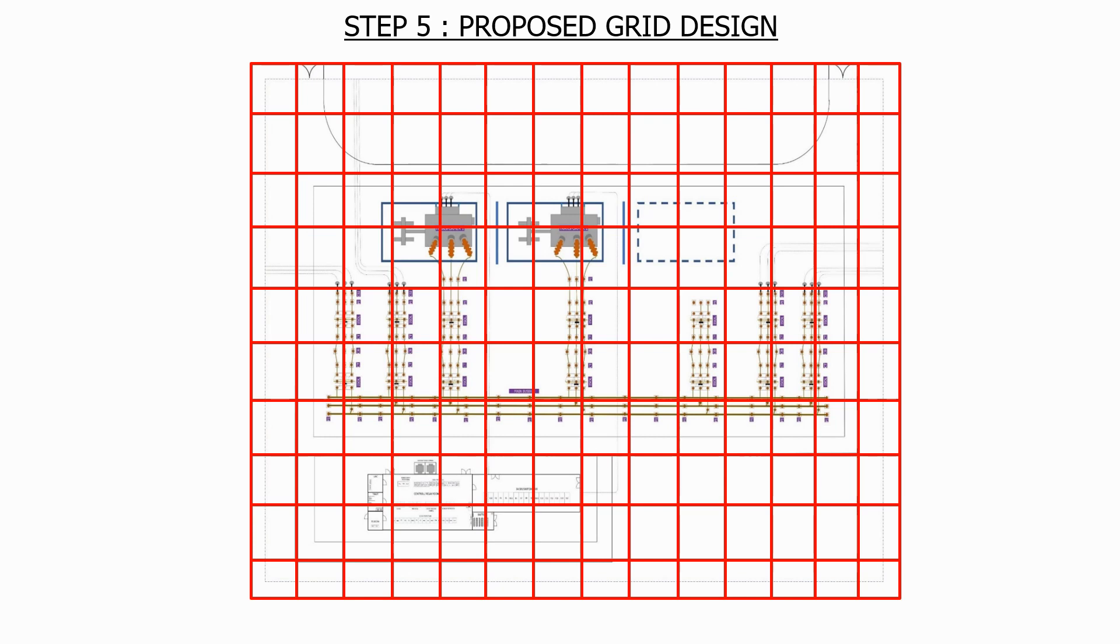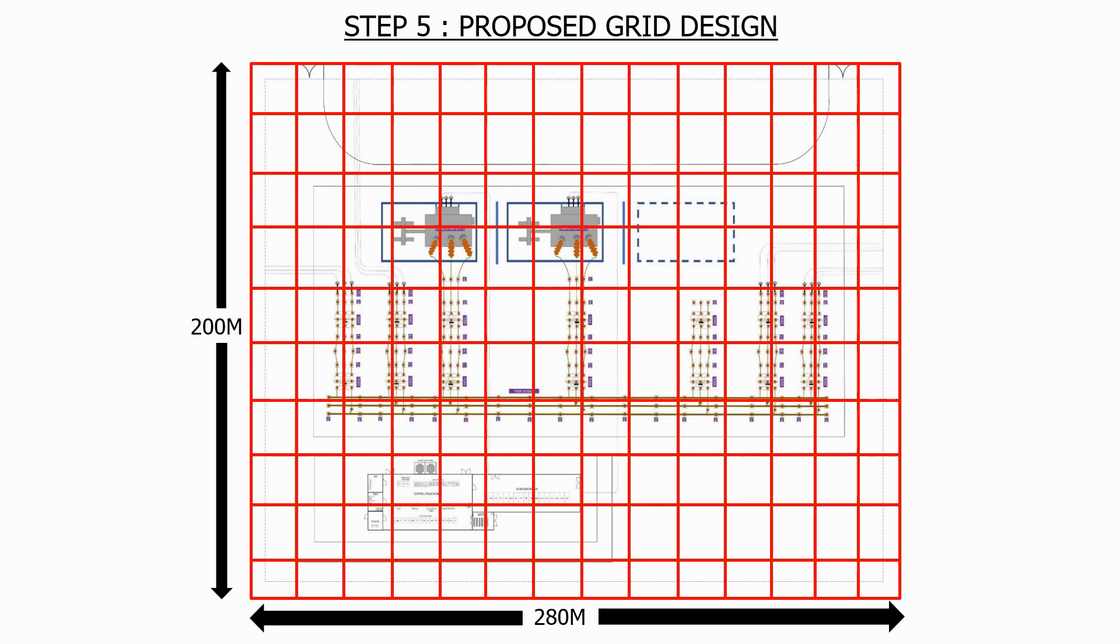So we can quickly define the overall dimensions. In this case, a width of 200 metres and a length of 280 metres. These dimensions are pretty much fixed as we're not going to build a bigger substation just so we can install a bigger grounding grid.